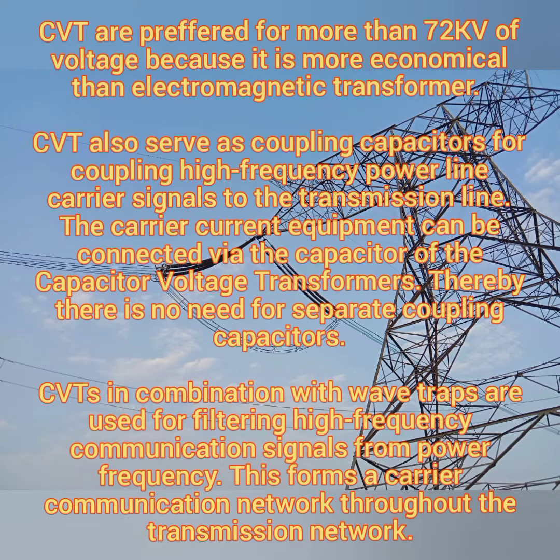The CVTs also serve as coupling capacitors for coupling higher frequency carrier signals, over the power frequency, to the transmission line. The carrier current equipment can be connected via the capacitors of the CVT, thereby there is no need for separate coupling capacitors. So, in transmission lines, higher frequency carrier signal transmission can be made through the CVT.